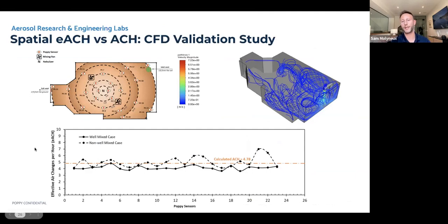So how do we validate this approach? We did it in two ways. First, we developed computational fluid modeling of aerosol motion in a simulated environment, so we could have a completely characterized and controlled environment and understand what the volumetric ACH would be for that room, given air coming in through a diffuser vent, or virtual diffuser vent, and being released out of a virtual return vent, and how that relates to particle concentrations over space and time in the room.